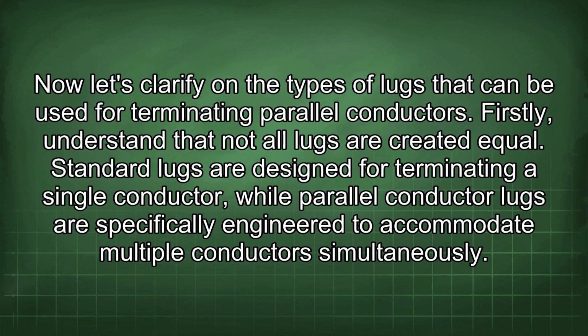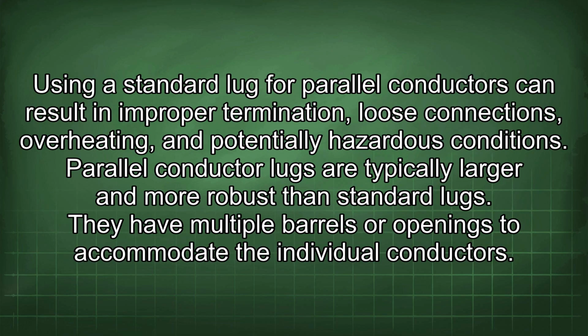Now let's clarify the types of lugs that can be used for terminating parallel conductors. Firstly, understand that not all lugs are created equal. Standard lugs are designed for terminating a single conductor, while parallel conductor lugs are specifically engineered to accommodate multiple conductors simultaneously. Using a standard lug for parallel conductors can result in improper termination, loose connections, overheating, and potentially hazardous conditions.